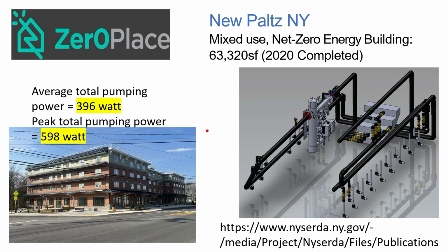That's why we pay attention to the pumping power. Because all those buildings are 100% cooling dominated. We're rejecting more heat into the loop field than we're getting out, normally. So we balance them with hot water to cool the loop field nicely in the summertime when we generate all hot water and pull the heat out for that. And the total pumping power at the very peak time at -6 degrees, when all the heat pumps were running, was 600 watts. 600. So you as engineers, please pay attention to the pumping power. We don't want additional heat in the loop field. Heat is the enemy.